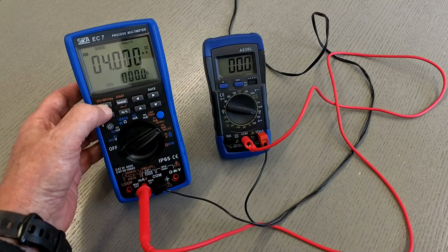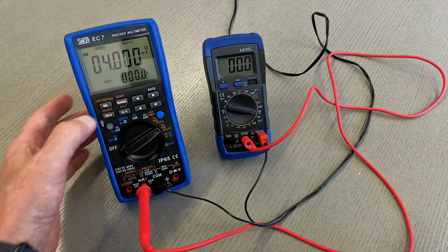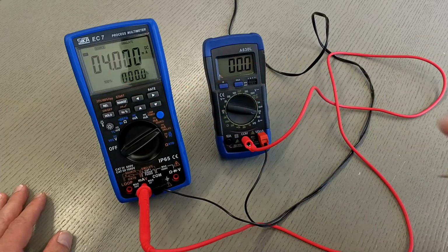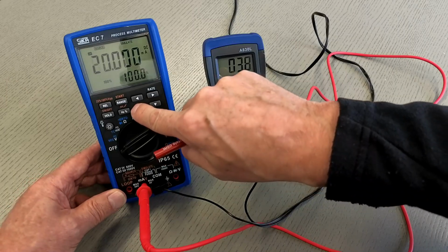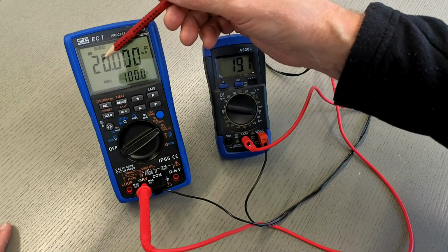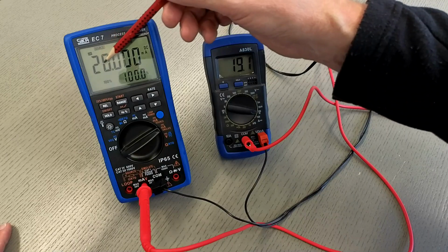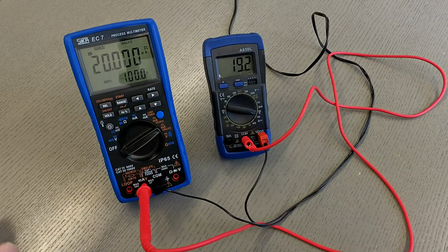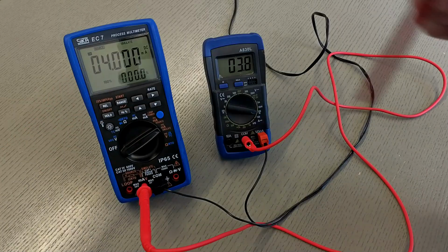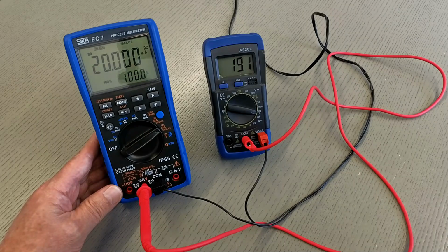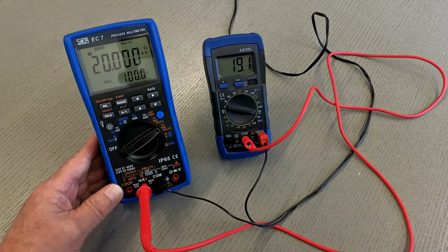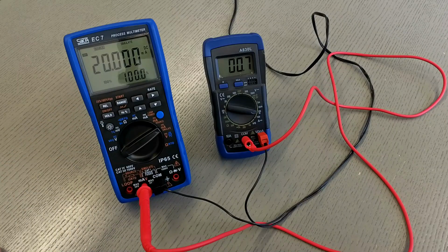I operate again this operating button, change over to 100, and then 100 is indicated. I switch on. I have the 4 milliamp, and if I increase now, I see immediately 100%, and 100% is related to 20 milliamp. If I decrease, I go down to 0. If I increase, I go up to 100%. I switch off again the loop current. The loop current is back to 0.